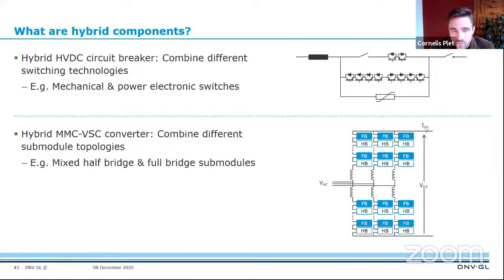That doesn't mean it's not possible. I'd like to refer to the same project I mentioned before, Wudongde in China, where the VSC link side converter is actually a hybrid MMC VSC converter. Also in Europe, there may be an application in point-to-point bipole offshore wind farm connections in order to handle metallic return faults.